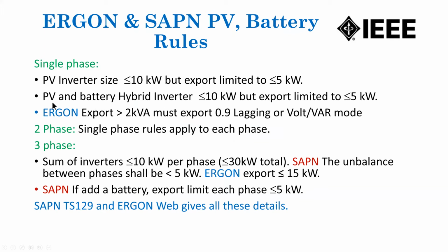If you've got a PV and a hybrid battery, exactly the same applies: 10 kilowatt, but export limit to 5 kilowatt. In North Queensland, if you export more than 2 kVA, then you must export lagging power, or your inverter must be capable of a volt-var mode, which means if the voltage gets too high, you export lagging power, and if it becomes too low, you export leading power. Single phase rules apply for each phase if you've got 2 phases. If you've got 3 phases, it's a little bit different. You're still limited to 10 kilowatt per phase, so 30 kilowatt total.